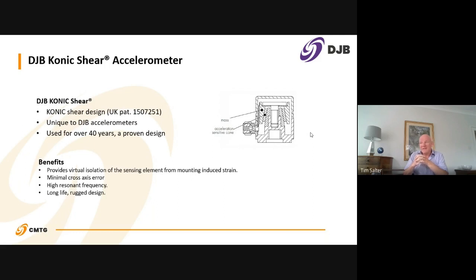isolation of the sensing element from mounting induced strain. If you mount an accelerometer using a stud and you over tighten it with normal accelerometers using the compression or shear, you can induce an error simply by how much you tighten the base, because you're putting a preload onto it. Konic Shear is virtually immune from that.